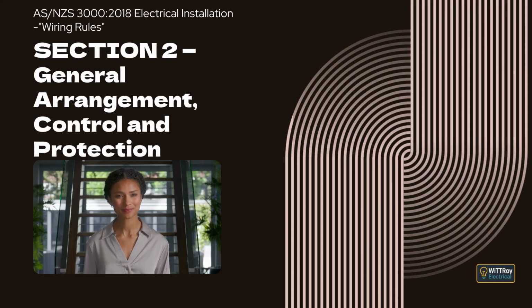For circuit breakers less than 250 amps, discrimination is generally considered to be achieved when the upstream breaker has a rating at least 1.5 times that of the downstream breaker, as long as both devices have the same curve type. The clause also describes how fuses and circuit breakers can be coordinated. For fuses used together, discrimination is usually achieved when the upstream fuse has a current rating 1.6 times that of the downstream fuse for overload, and at least 2 times for short-circuit currents.